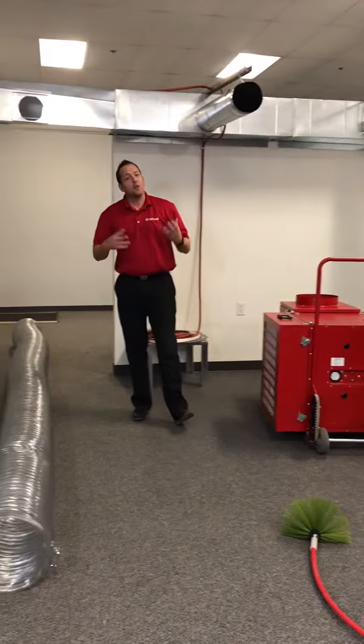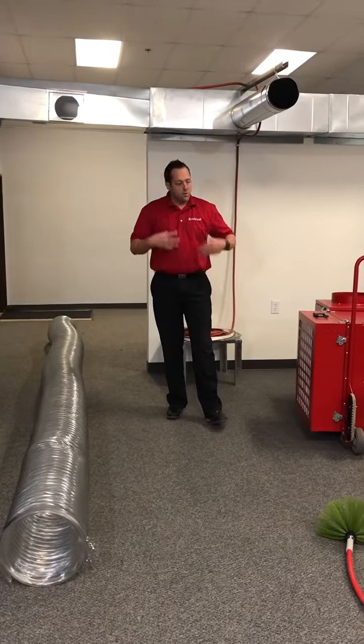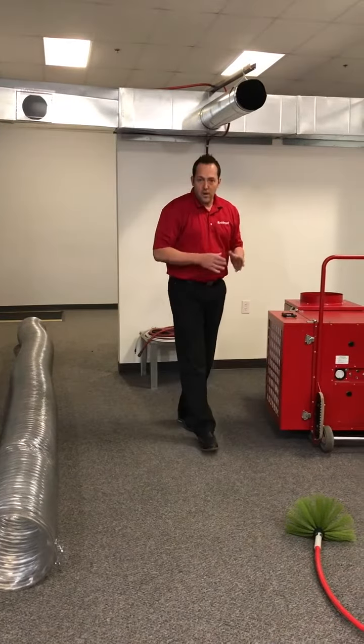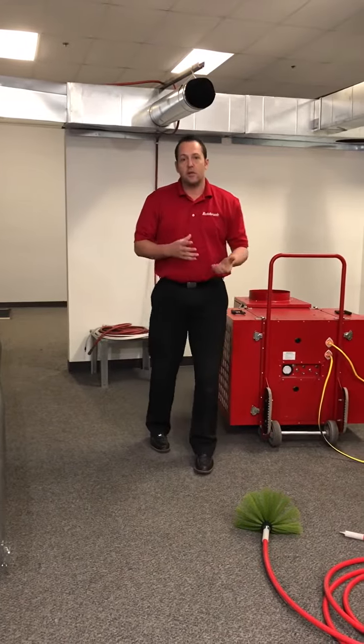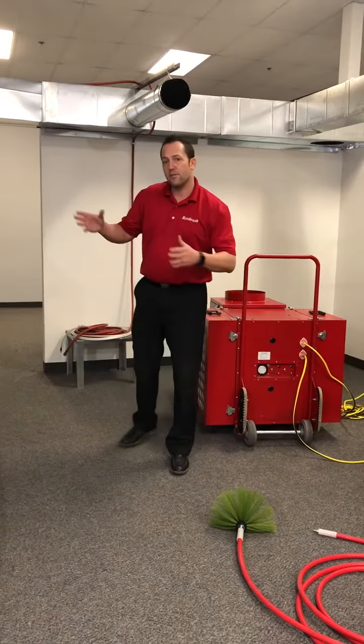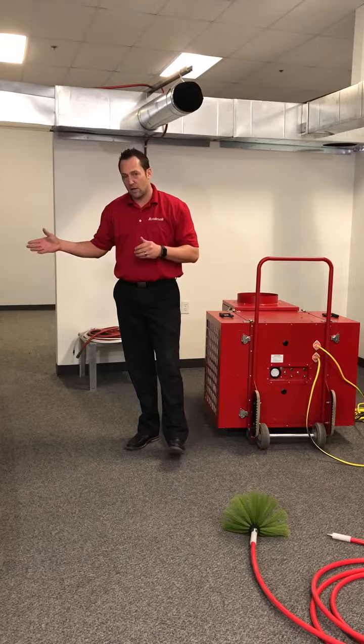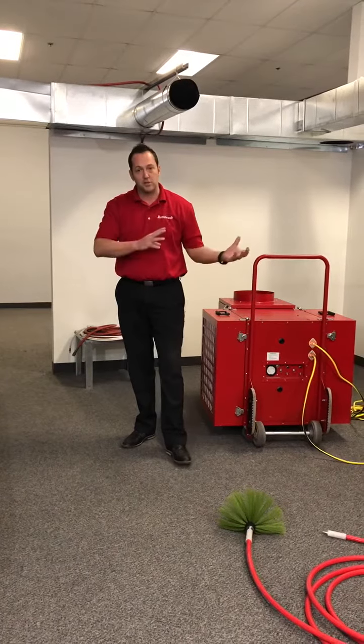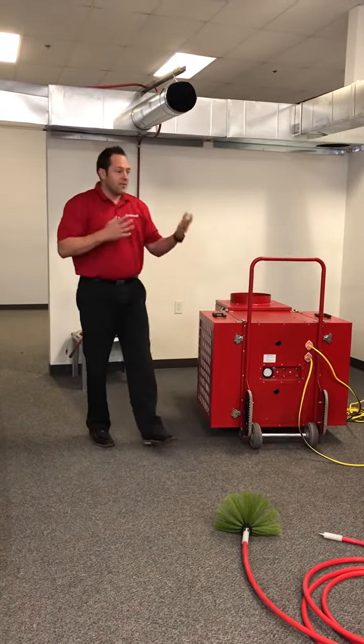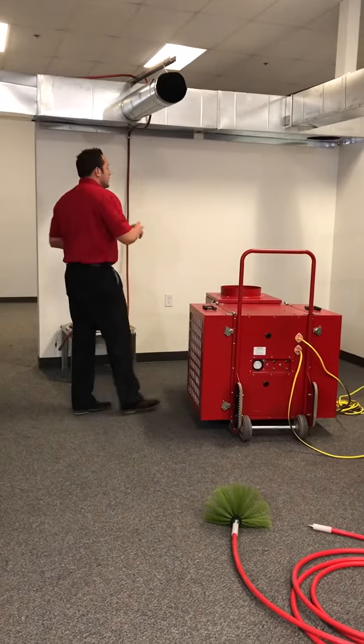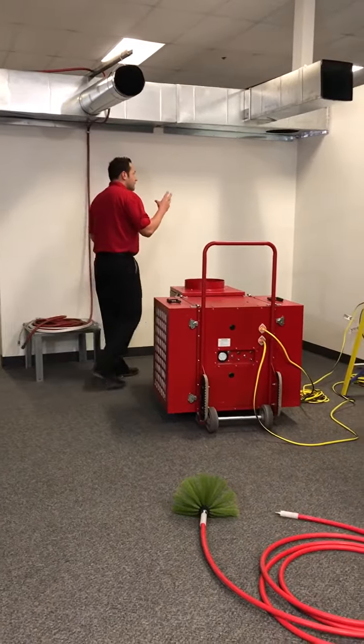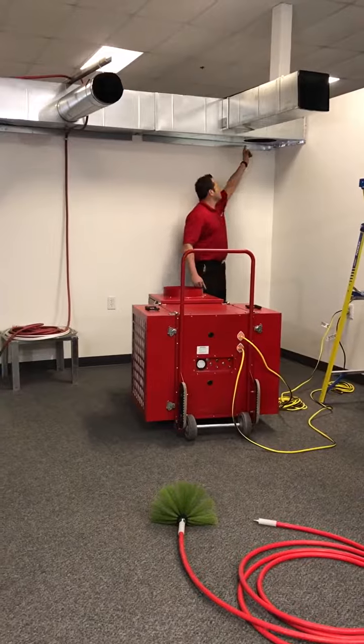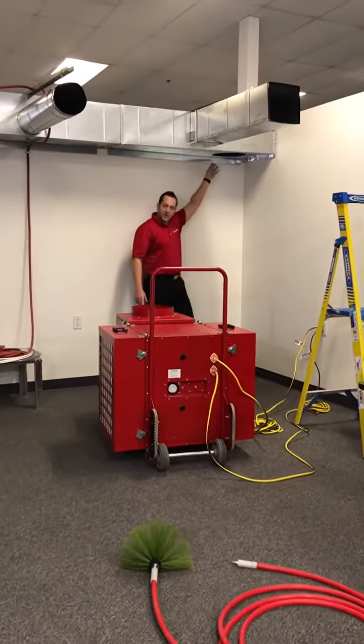Now, assuming you don't have a Rotobrush, this is the process we'll walk through. Just like it showed in the owner's manual, you're going to start from the furthest register from the air handler, working your way back to the closest to the air handler. The first thing you're going to do is go to the actual air handler itself and cut an access hole, 8 to 10 inches, in the ductwork.